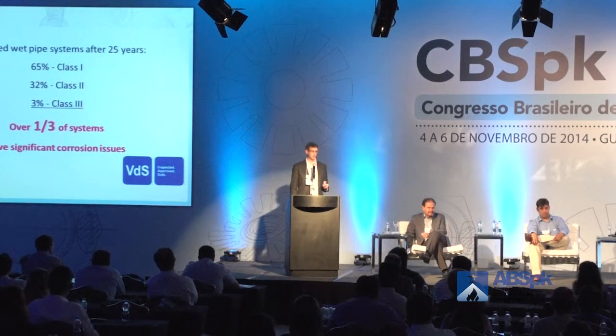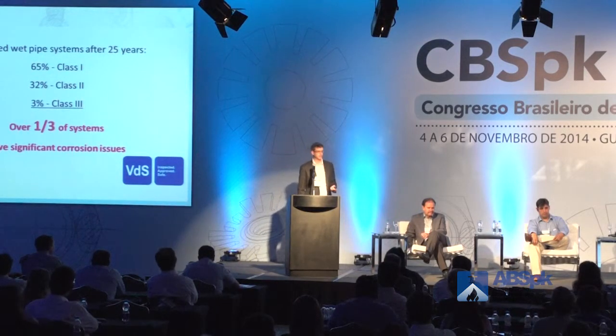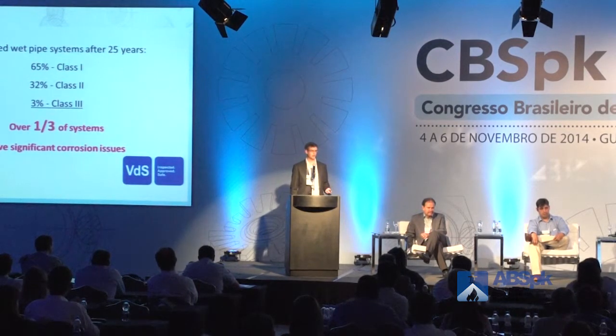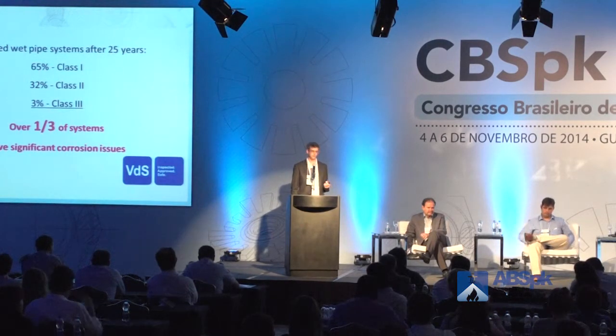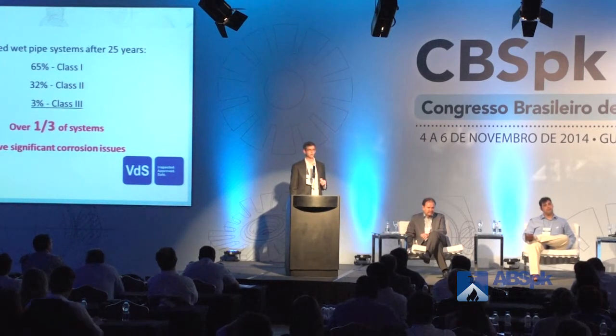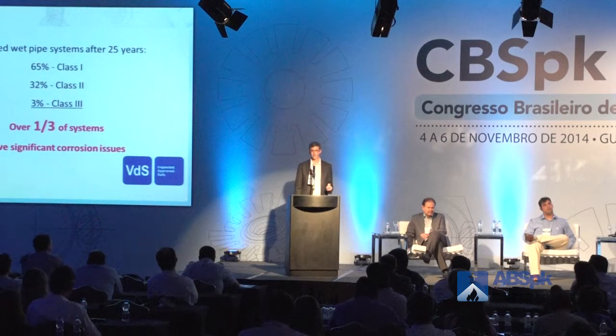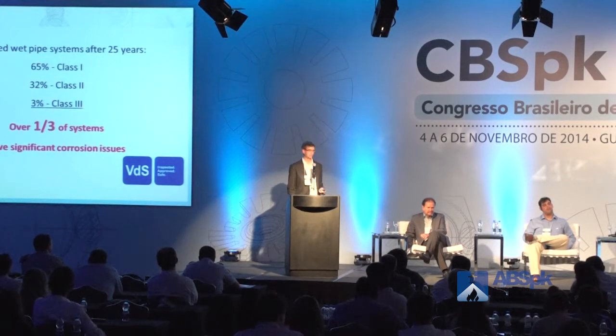So to give you an example of how prevalent this is in the fire sprinkler market, the results of them looking at wet systems: what they actually found was after being installed for 25 years, about a third of those systems had enough corrosion going in. They actually had to replace pipe or replace the entire sprinkler system at a cost to the building owner.